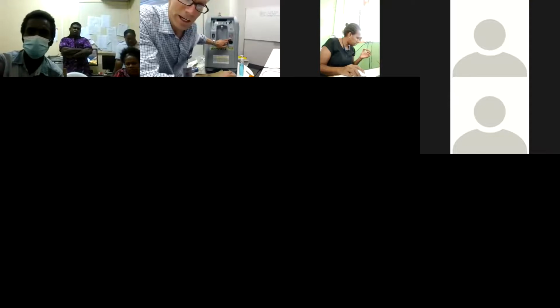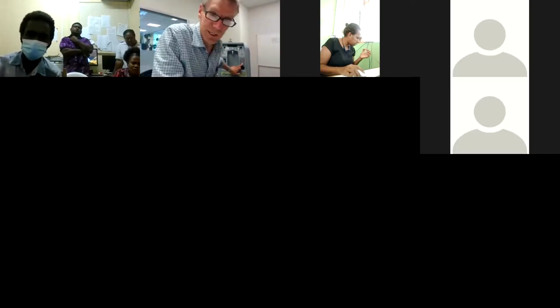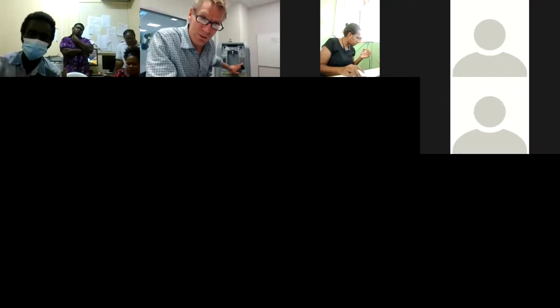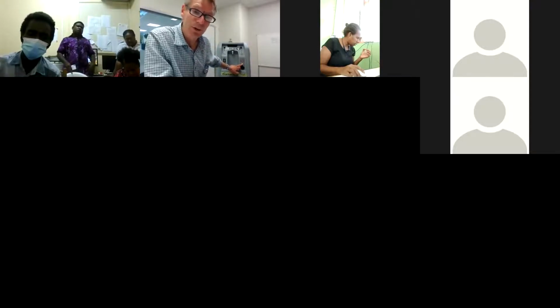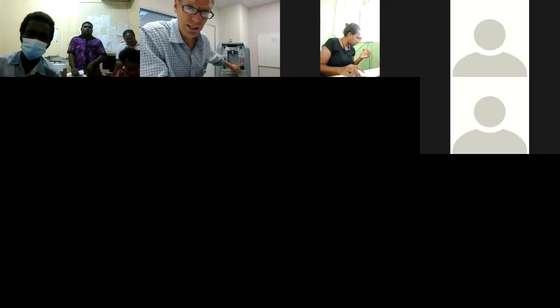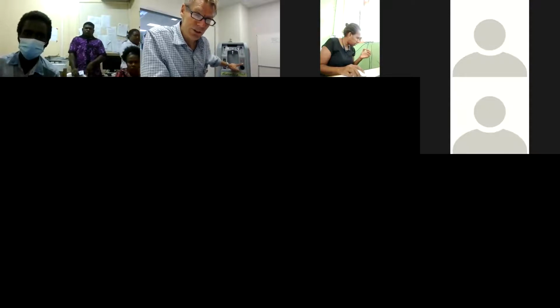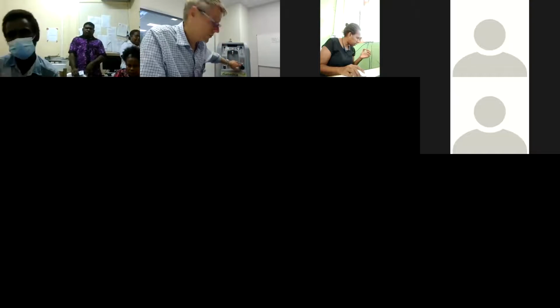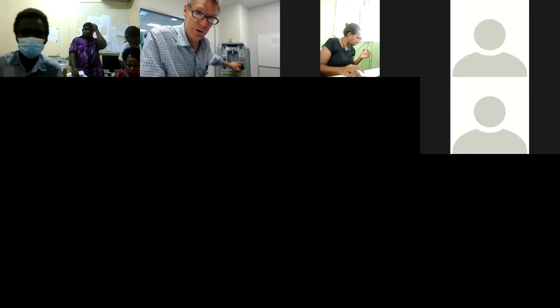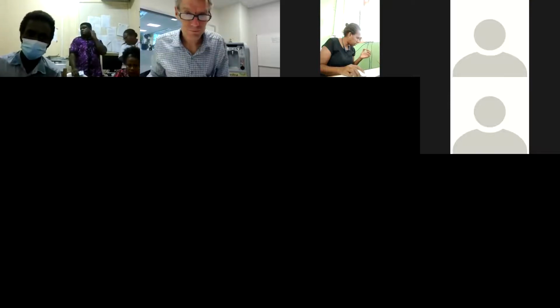But the real reason for this light is to see whether the concentrator is producing enough oxygen. All right? If the light stays on, then the concentrator is not producing enough oxygen. Sometimes it takes 2 to 5 minutes for that light to go off. But when the light goes off, it tells you that the concentrator is producing enough oxygen. Okay, so at the moment that light's still on. So my concentrator at the moment is not producing more than 85% oxygen, and that's just because it takes time for the concentrator to build up to be producing high concentration oxygen. But you'll see that light will go off shortly. I'll just share my screen again.